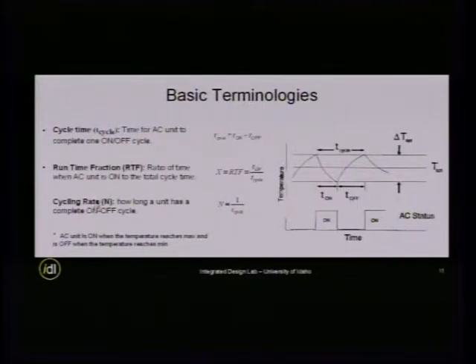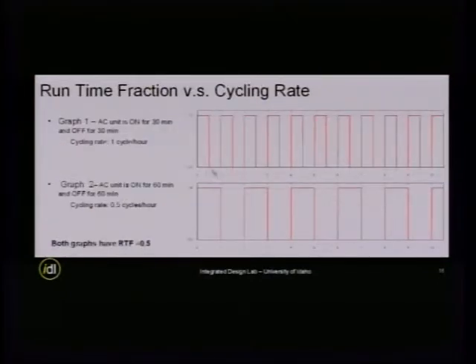And then we have another important parameter, which is the cycling rate. The cycling rate is simply the inverse of the T cycle. So to give you the difference between the runtime fraction and the cycling rate, there's one unit here that cycles 30 minutes on, followed by 30 minutes off. We know that the cycling rate will be one cycle per hour. Another unit has 1 hour on and then 1 hour off. The cycling rate is half a cycle per hour. But both have the same runtime fraction, which is 0.5.